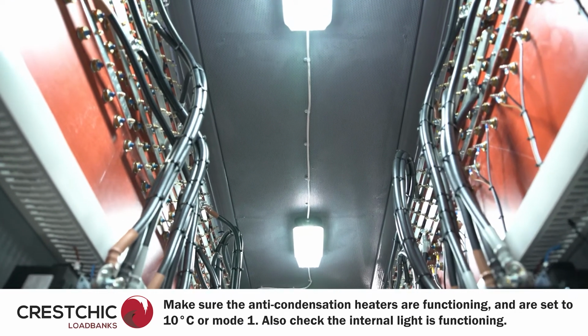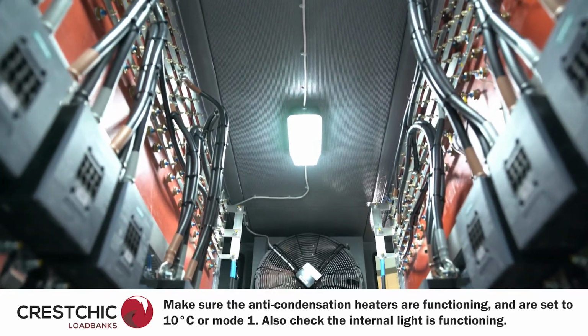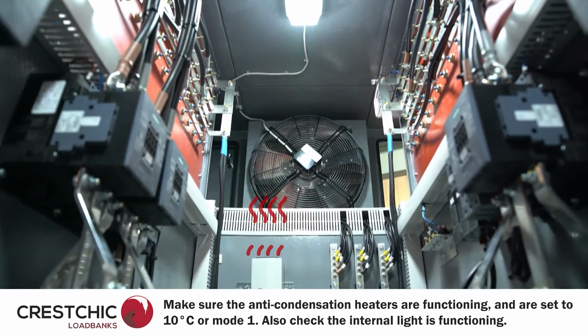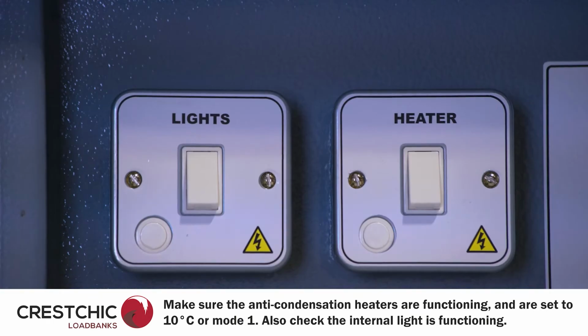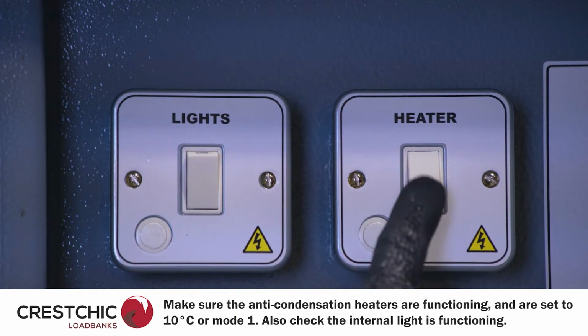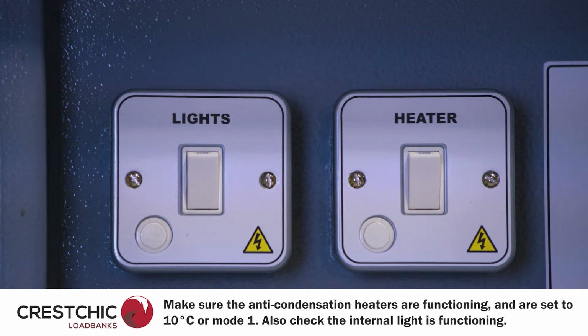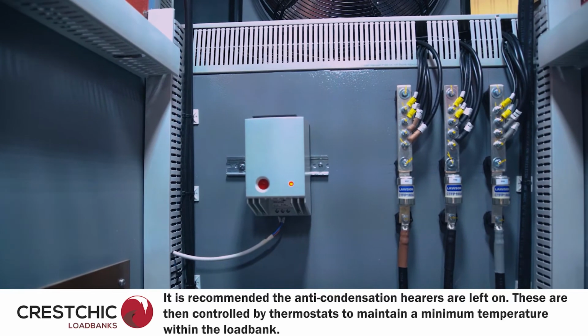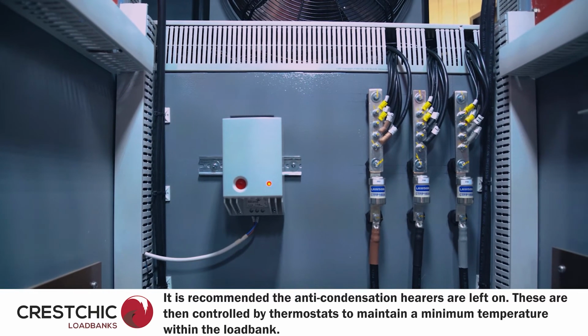Now the supply is on for the anti-condensation heaters and lights, the heaters should be checked for function, along with the internal light. There are switches for both of these. It is recommended that the anti-condensation heaters are left on. These are then controlled by thermostats to maintain a minimum temperature.